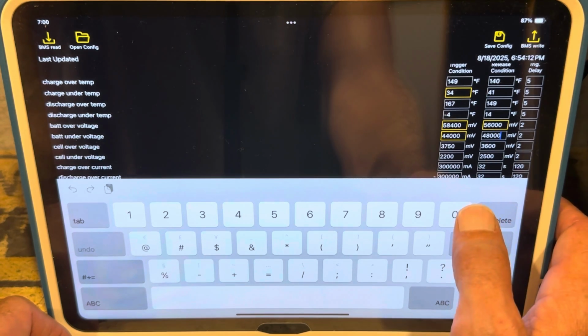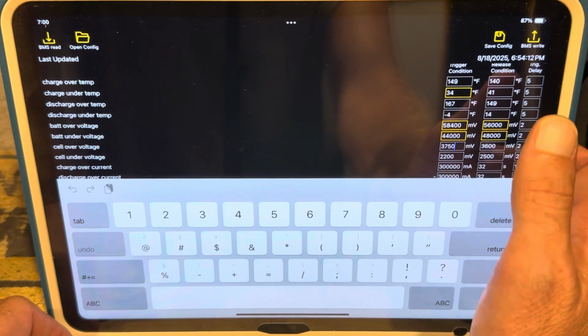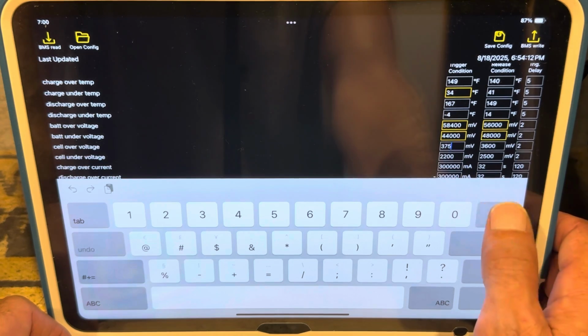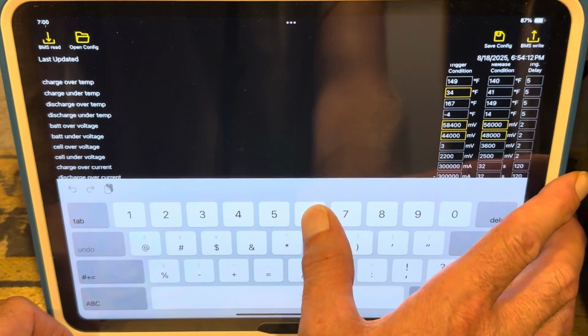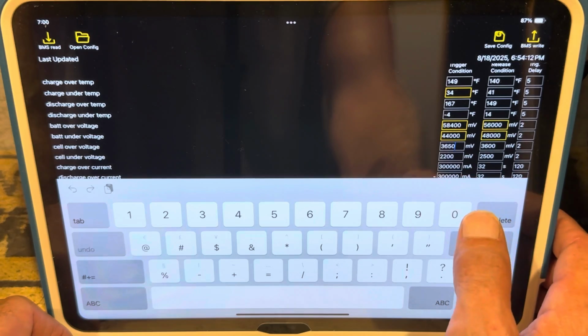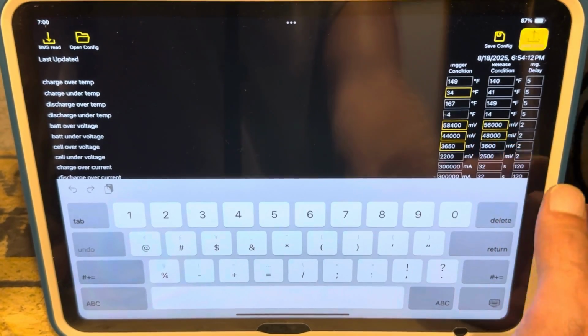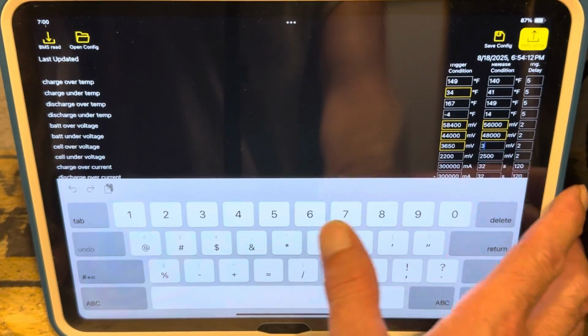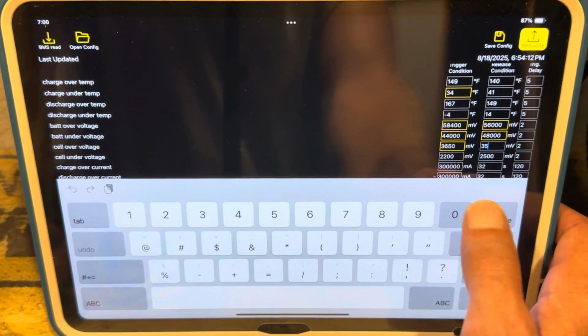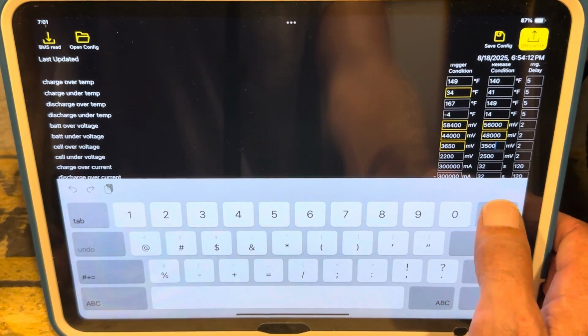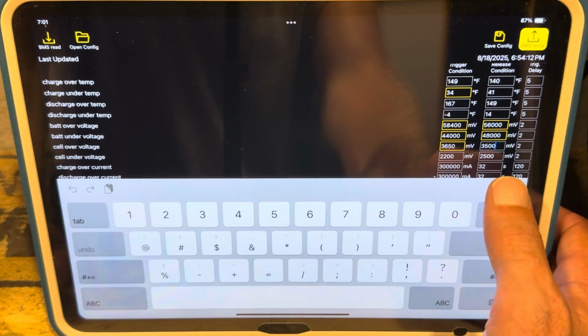And then the cell over voltage condition, set at 3.75 per cell - I'm going to set it back to 3.65 volts per cell. And I'll set the release condition at 3.5 volts per cell. The delays should be fine on all this.